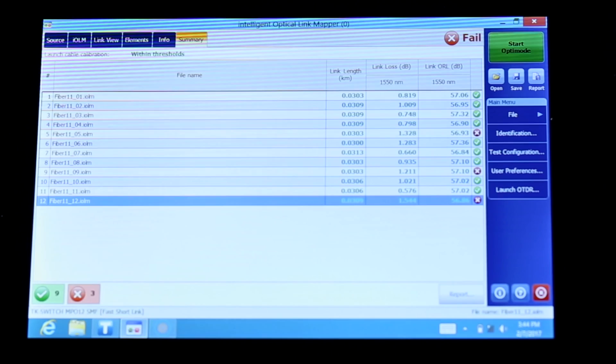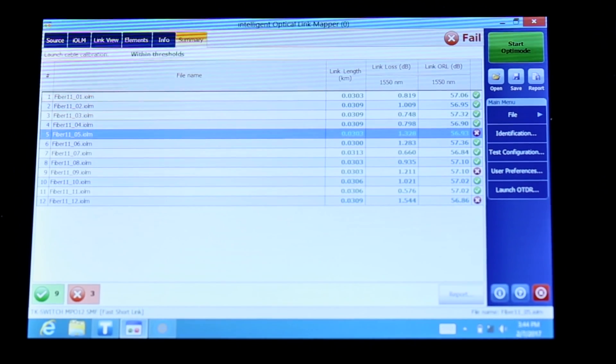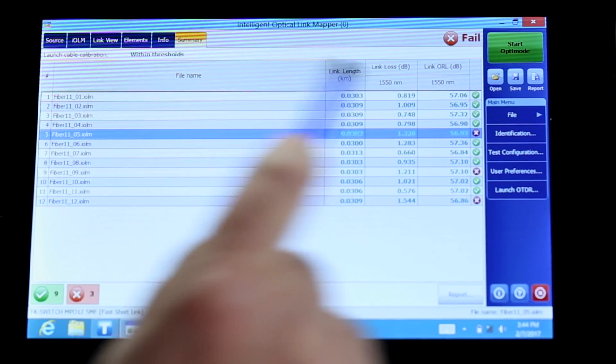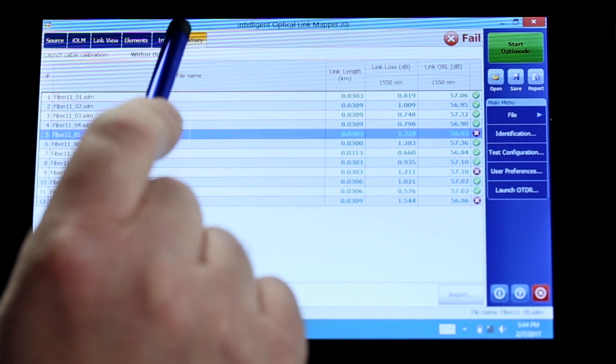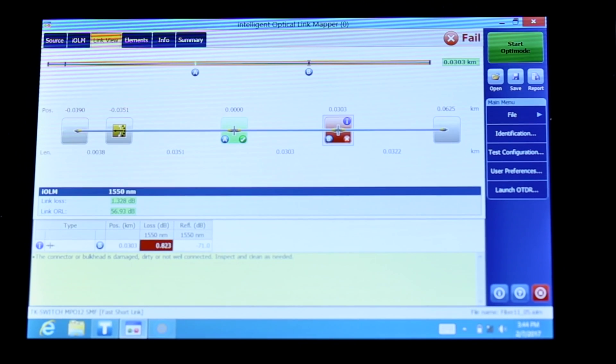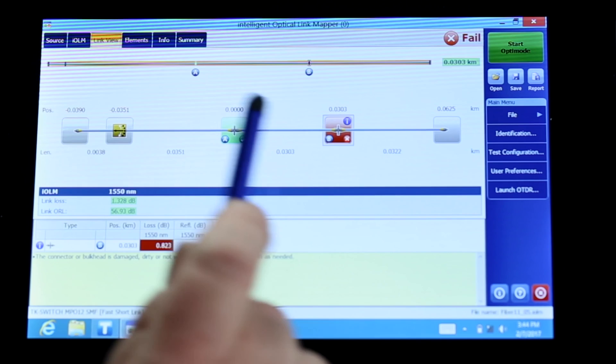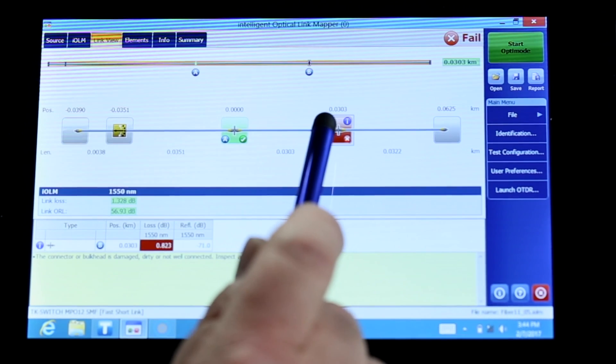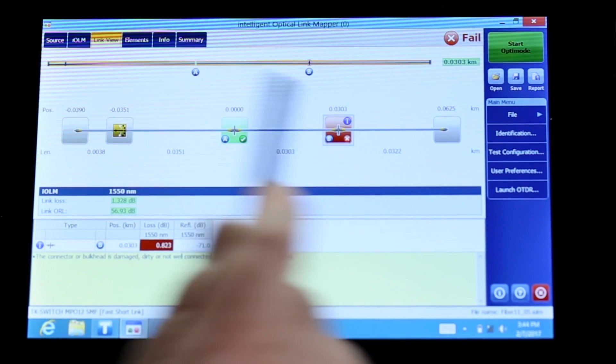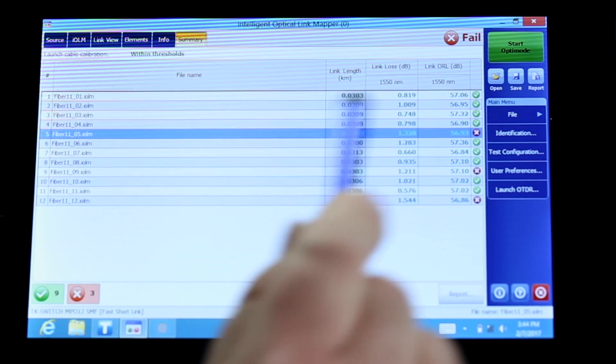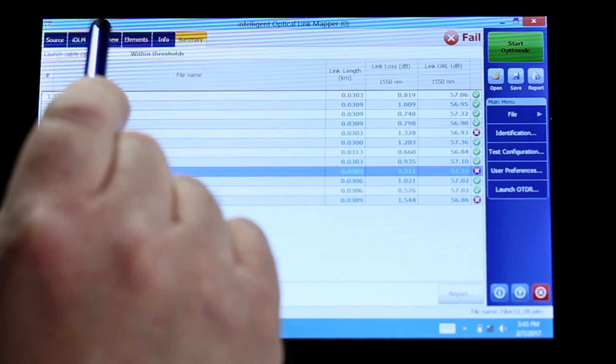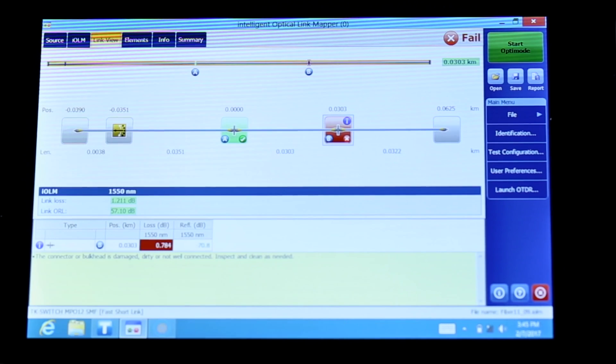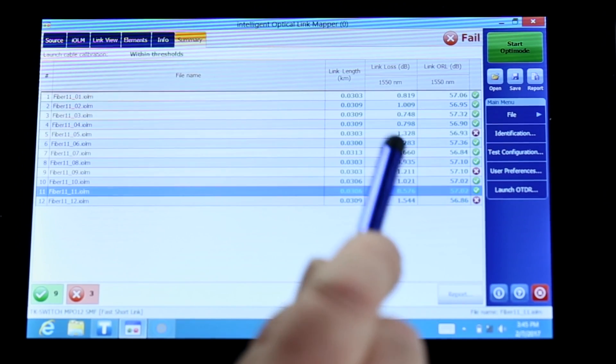Let's go to the failed fiber. I select the fiber. The touch screen FTB1 allows me to do that very easily. I select the first fiber and I switch from summary to link view just to validate which connector, from the A1 and the B1, which one is bad. We see that the first failed fiber is the connector B. That's what you need to understand first. You just scan the different failed fibers one after the other and you see again connector B. Last one of the three fails, connector B again.